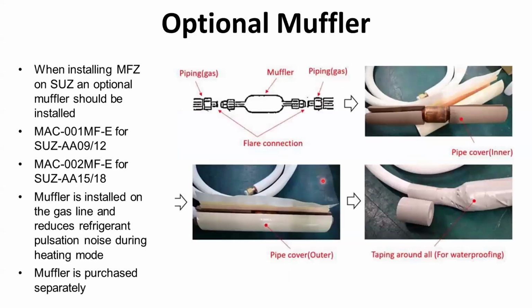Now what's changed also, so here we have this optional muffler. So when installing an MFZ unit on an SUZ, an optional muffler should be installed. So when you're doing this scenario right here, this is the floor unit, the MFZ, and then this is the SUZ Universal Outdoor Unit. This is an optional muffler. It doesn't come with the equipment. Here's the part number. So this one here, this part number is for the 3/8 muffler. This part number here is for the 1/2 inch muffler. Muffler is installed on the gas line and reduces refrigerant pulsation noise during heating mode.